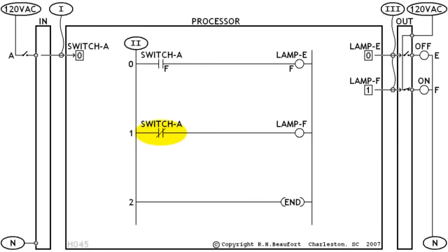Then the processor comes to this XIO instruction. The rule says, go look for a zero. Do we have a zero? Yes. So this is true. And so this OTE has true coming in. And the rule says, go write a one.